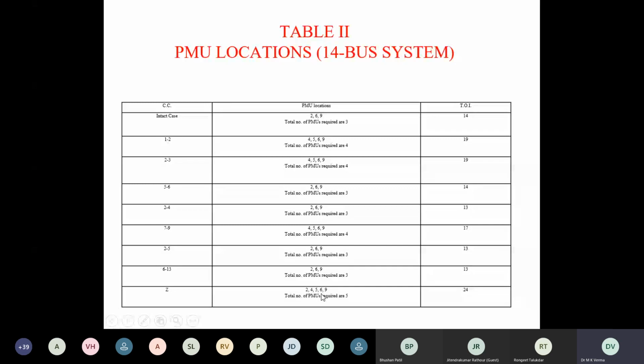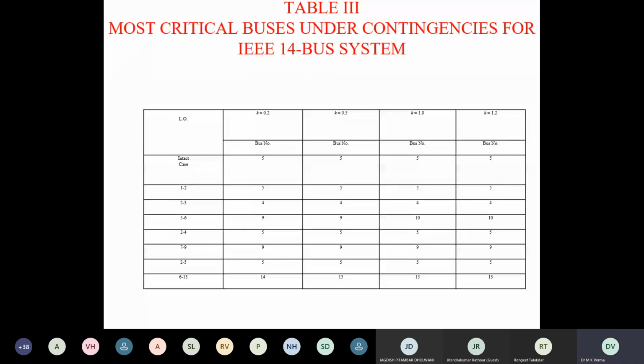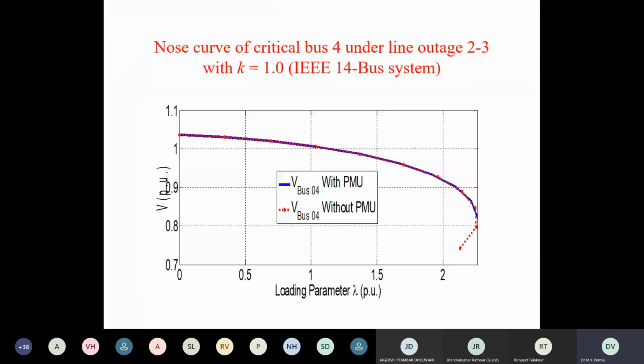With PMUs placed at these 5 buses, he got an observability index of 24, much above 14. So even if some PMUs are lost due to contingencies, or some data is lost, it is still able to maintain security of the system and completely observe the system. Then you obtain the nose curve of critical bus 4 with PMU and without PMU, with almost the same results.